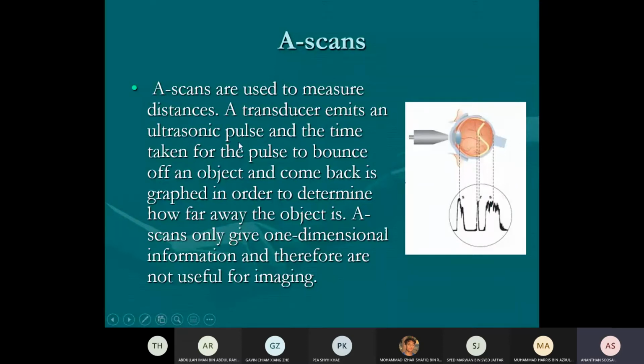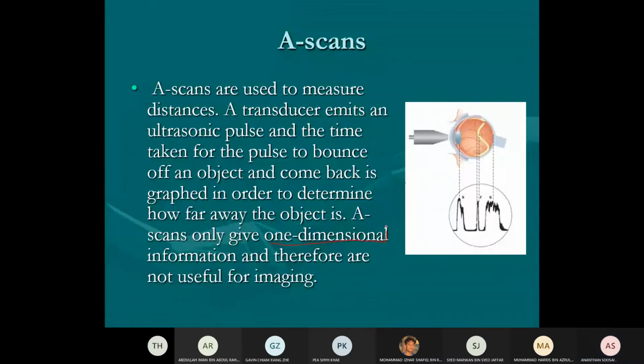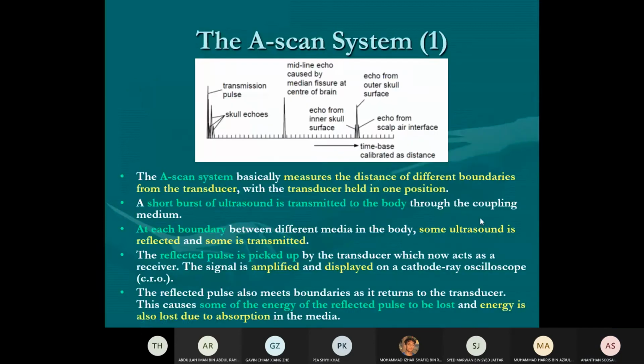A transducer emits an ultrasonic pulse, and the time taken for the pulse to bounce off an object and come back is graphed in order to determine how far away the object is. So A scan only gives one dimension. Remember, A scan is a one dimensional scan. Therefore, it is only used to tell the depth, how deep the layers are. The A scan system measures the distance of the different boundaries from the transducer. The transducer is held in one position.